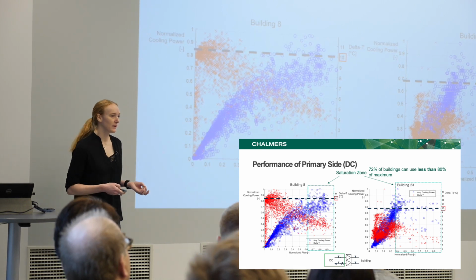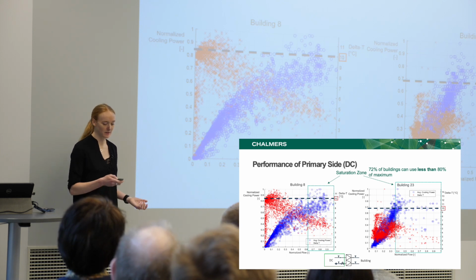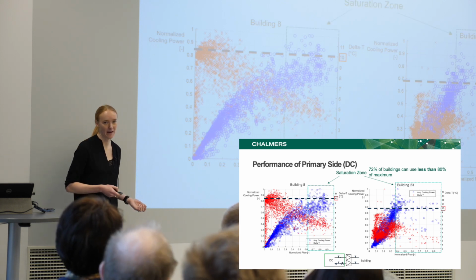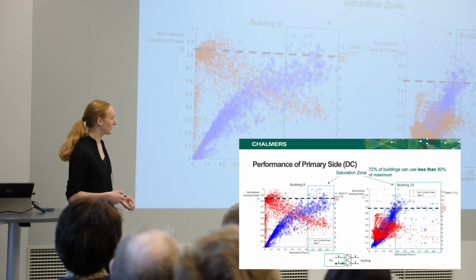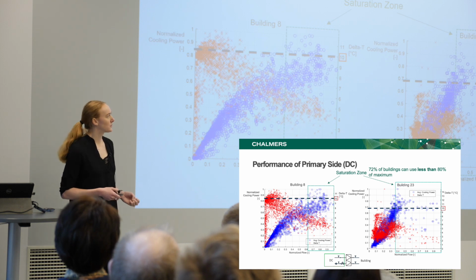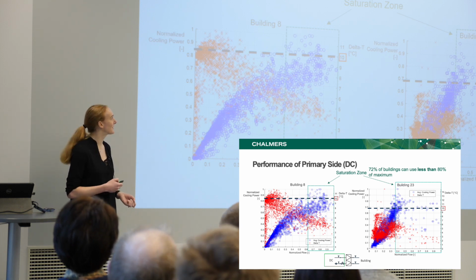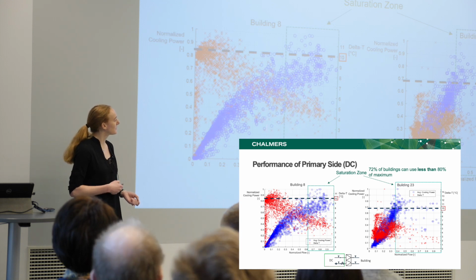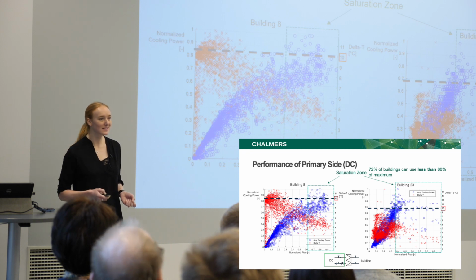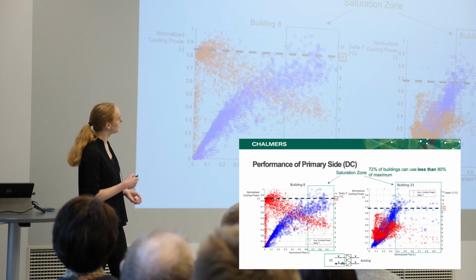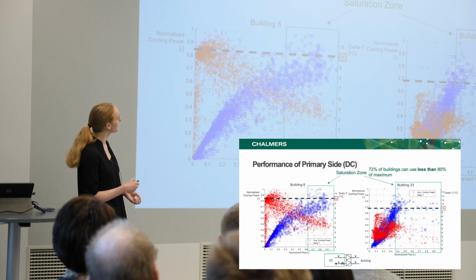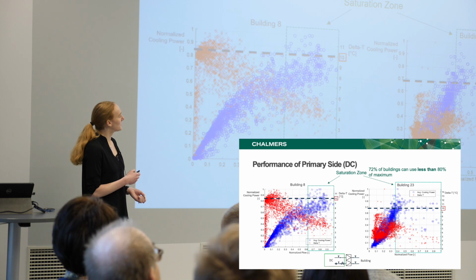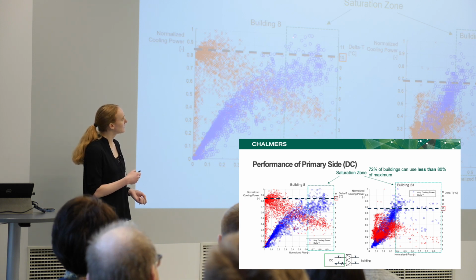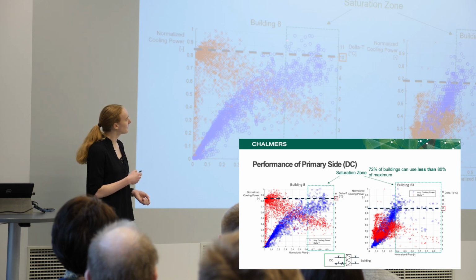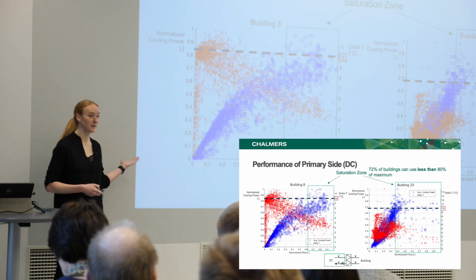However, what's important is what the production plant is struggling with: when everyone has the highest cooling demand. And that is, of course, when the flow is the highest. What was observed for almost all the buildings is this so-called saturation zone, which I have illustrated by these boxes. For the highest cooling power, you can see these blue dots hit the number 1 up here on both axes. Whatever flow rate more than this point is just a waste of flow, because you get the maximum cooling power for a flow that is around 70% of the used maximum in this substation.